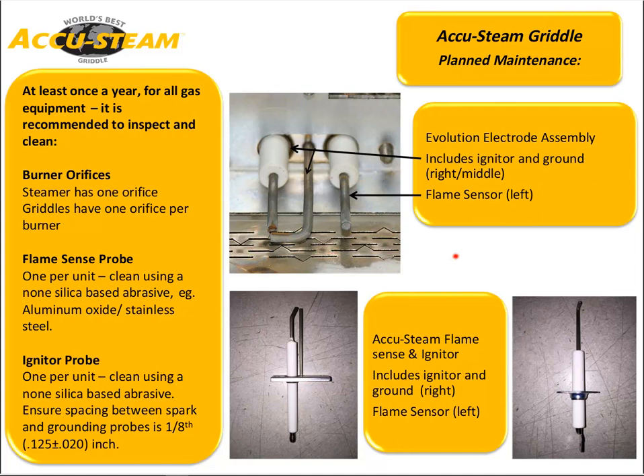If you're having issues with gas equipment, you will always want to verify that your burner orifices are clear. There is one in the steamer to the right of the main valve, and there is one per burner on the griddle. Make sure all of your probes are cleaned, especially if you have a low flame sense, and that should be done at least once a year.